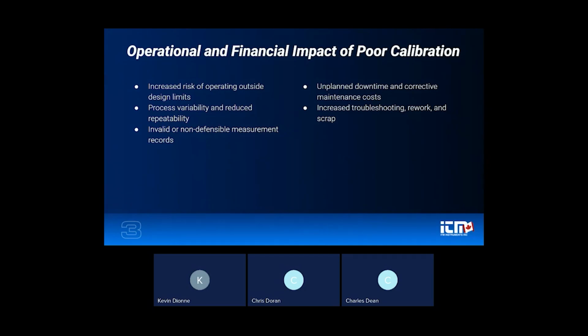From a compliance and quality perspective, uncalibrated or undocumented instruments create risk even if the process appears to be operating normally, because your measurement data collected during that period may be considered invalid or non-defensible during your audits or your inspections. Financially, these impacts tend to be indirect and cumulative rather than immediate, but the unplanned downtime and the emergency maintenance that's required usually increases the operating costs significantly and causes major issues. So taken together, skipping calibration doesn't just increase technical risk, it erodes your operation, and it drives your avoidable costs of maintenance and production through the roof.